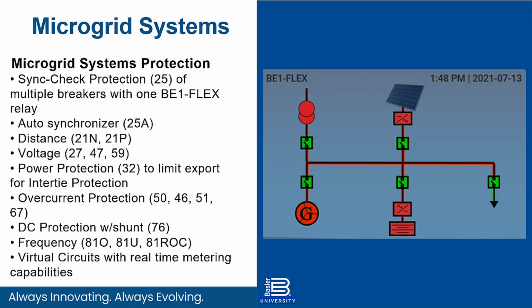Another thing that's very important about a microgrid type application is going to be automatic synchronization. So when you have multiple sources available, in this particular example we have a utility power source up at the top left, let's say a backup generator bottom left, a solar panel, and maybe even a battery system bottom middle. Any of those could potentially power and synchronize that load, and therefore you have to be able to mix and match and be able to synchronize to a wide variety of different system configurations in order to manage that system.